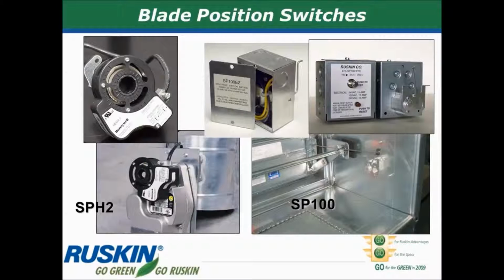In a modern building, the building management system likes to be wired into all the different components of the HVAC systems, bring it back to the central computer. And so with our life safety dampers, quite often we need indicator switches to tell us what the damper is doing. This slide right here shows some of the different options that are available that give us a signal of what the blade position is, instead of having to inspect every damper, because of course some of them are mounted so deep into the structure of the building it's very hard to get to. When we have these blade position indicator switches that are wired back to the central computer, we can not only know for sure what the blades are doing, if they're in the open or closed position, but also cycle test them remotely, as should be done quite often, to make sure the damper will operate.